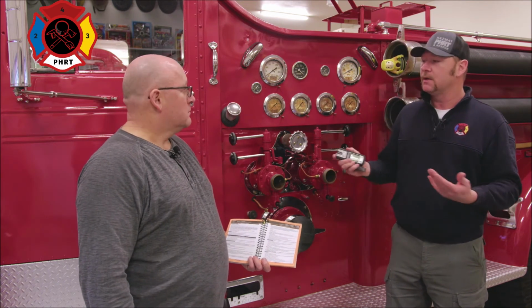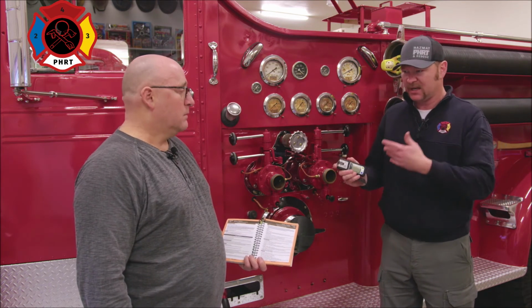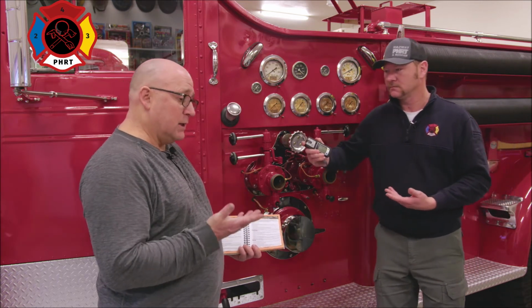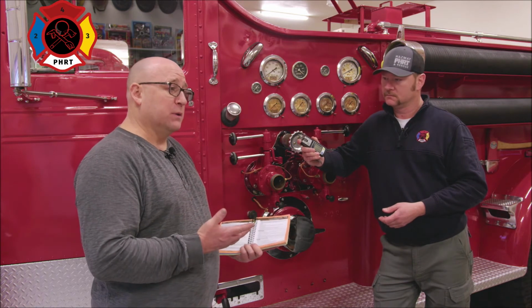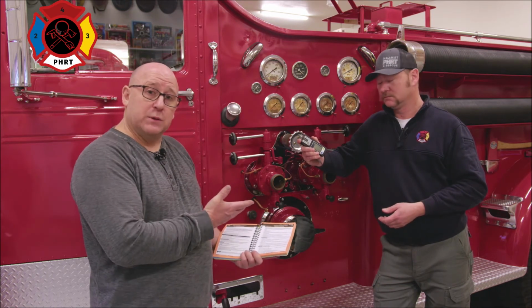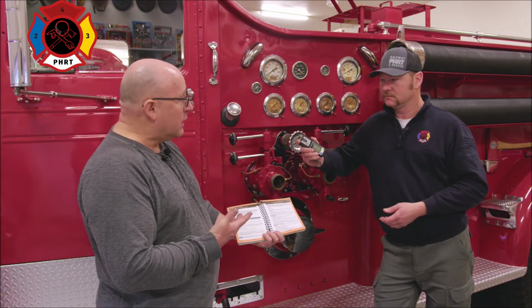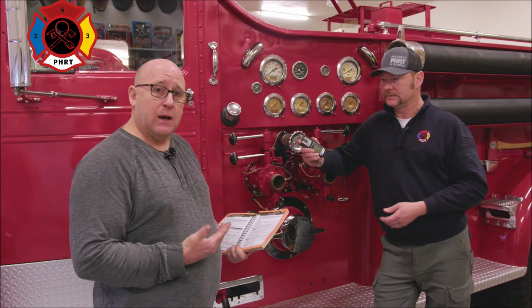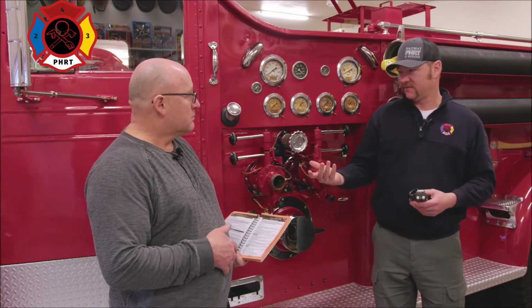Yes. And now what are we reading and what are we trying to find for these types of events? Are we looking at carbon monoxide, hydrogen sulfide, hydrogen cyanide, or what are we looking at? Well, primarily we're going to look for the lower explosive limit, which carries some misconceptions. So we're not looking for the lower explosive limit. This doesn't alarm at a lower explosive limit. This alarms at 10% of the lower explosive limit. And that gives us a warning to make sure we stay back before we get into the dangerous atmospheres. So a good 10 to 1 protection factor that we see, yes.